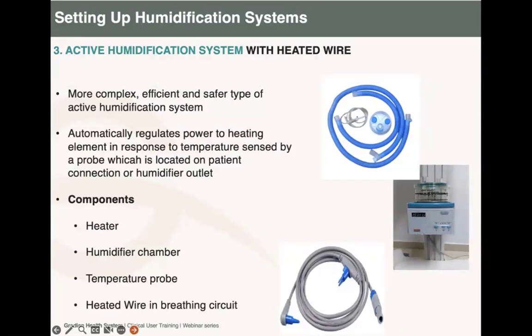So by using this heated wire type of humidification, we can avoid loss of temperature and loss of moisture, because the temperature is automatically regulated through the thermometer, which is located at the heated wires. Its components include the heater, humidifier chamber, temperature probe, and heated wire in a breathing circuit. So although this one is more complex, it's an efficient and safer type of active humidification system compared to the one without heated wire. Next slide.